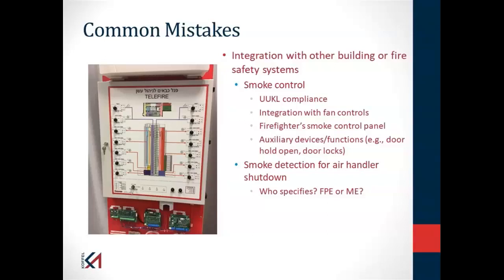The second major point: smoke detection for air handler shutdown. Sometimes in the design team, fingers get pointed at each other - well, the fire protection engineer should have done that, or no, the mechanical engineer should have done it. The point is, the code says it has to be done; it doesn't necessarily say who on the design team does it. So you want to make sure that happens.